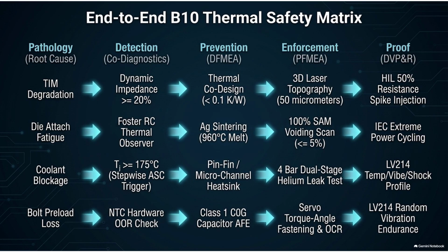The physical destruction of the inverter is imminent and unavoidable if the system doesn't react. And the pass-fail criteria are just as intense as the test itself. The digital twin software must detect the fault instantly, bypassing the physical sensor lag. It must drop the system into that stepwise active short-circuit safe state we discussed in under 60 milliseconds. That 60 millisecond window is rigid.